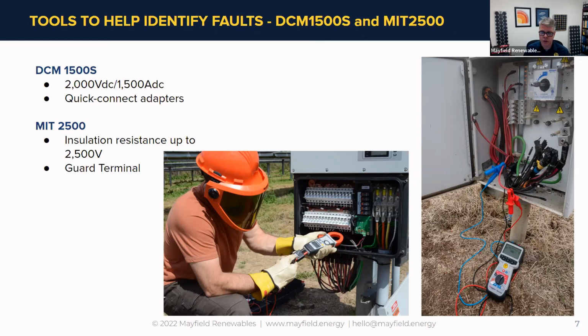Utilizing the DCM multimeter is one of the go-to methods for locating ground faults. Once you're able to isolate strings or conductors, you can check line to line, positive to negative, and then positive to ground, negative to ground. By knowing the string length and the voltage of each individual module, you can use those three different points to help locate the fault. It's not always perfect, but it's one of the tools in the toolkit when we talk about ground fault location.